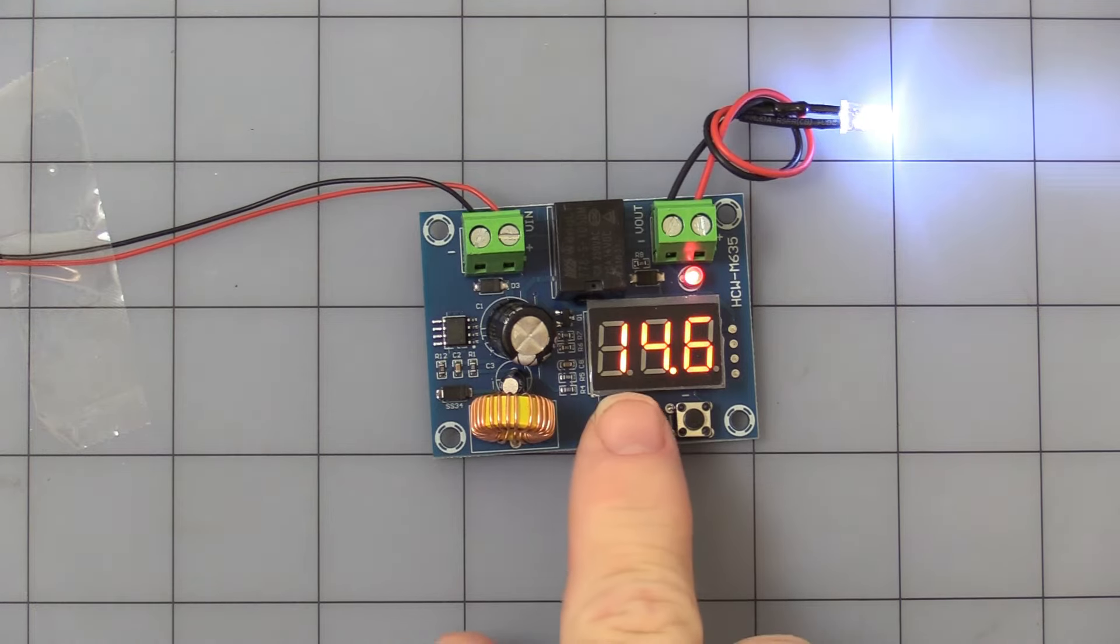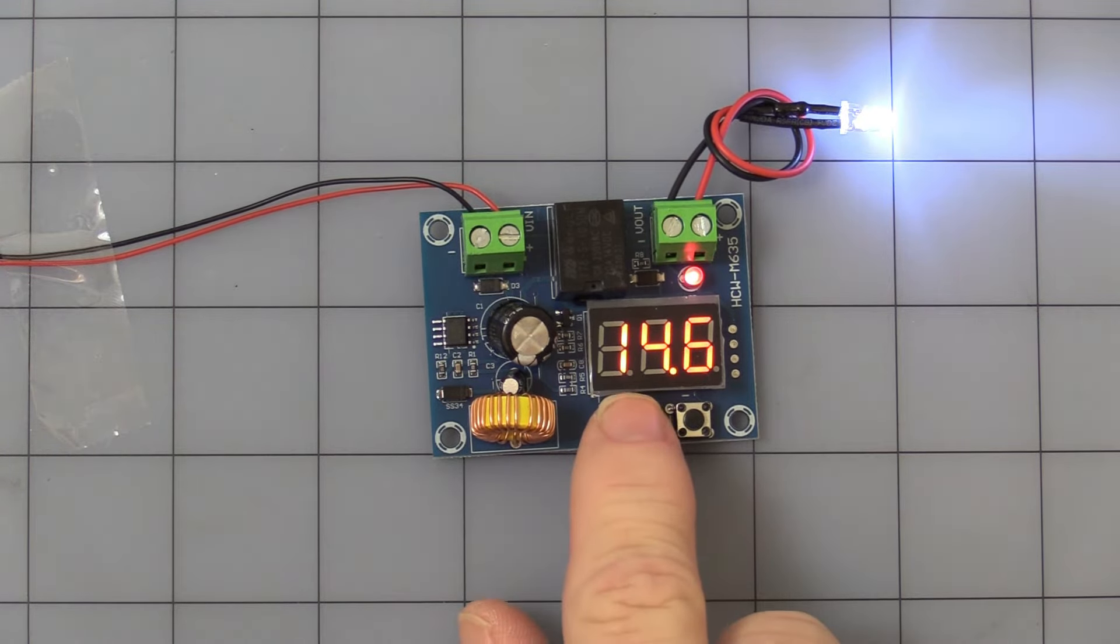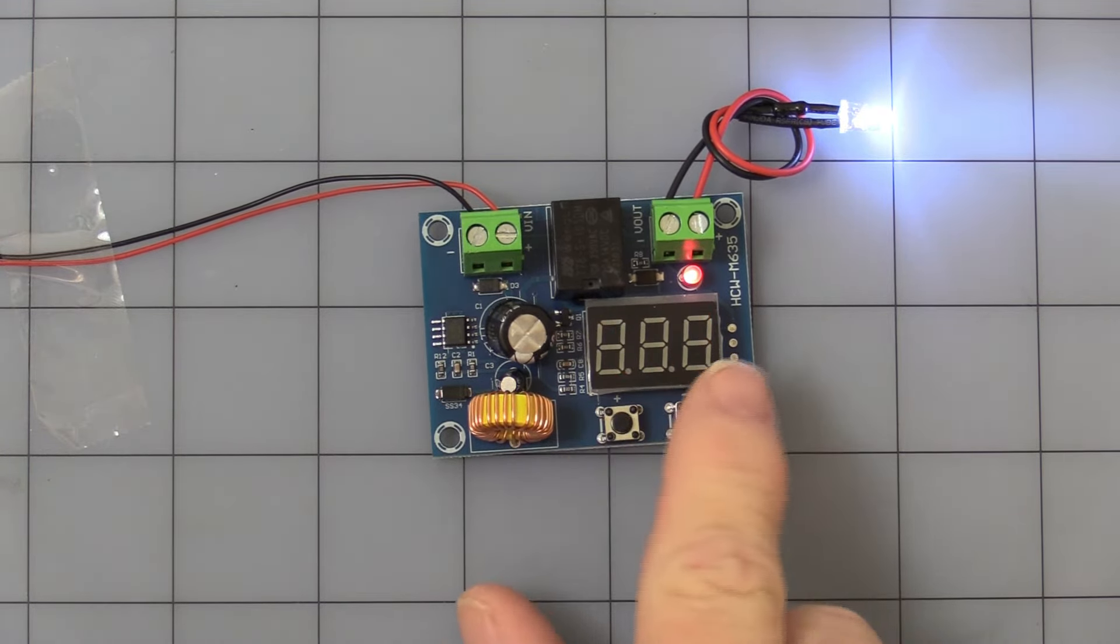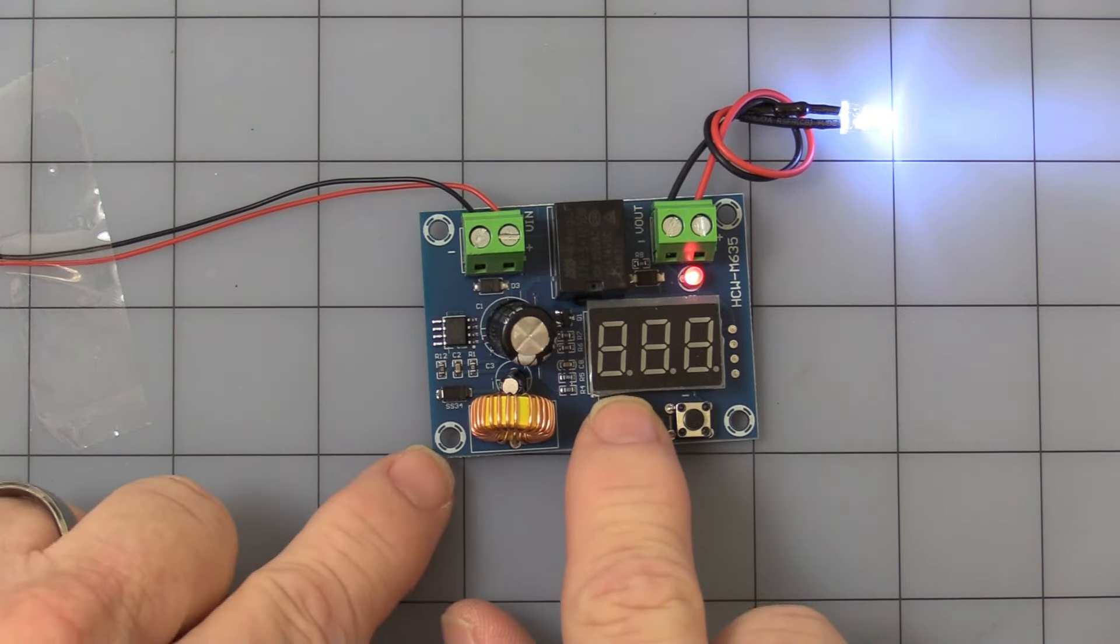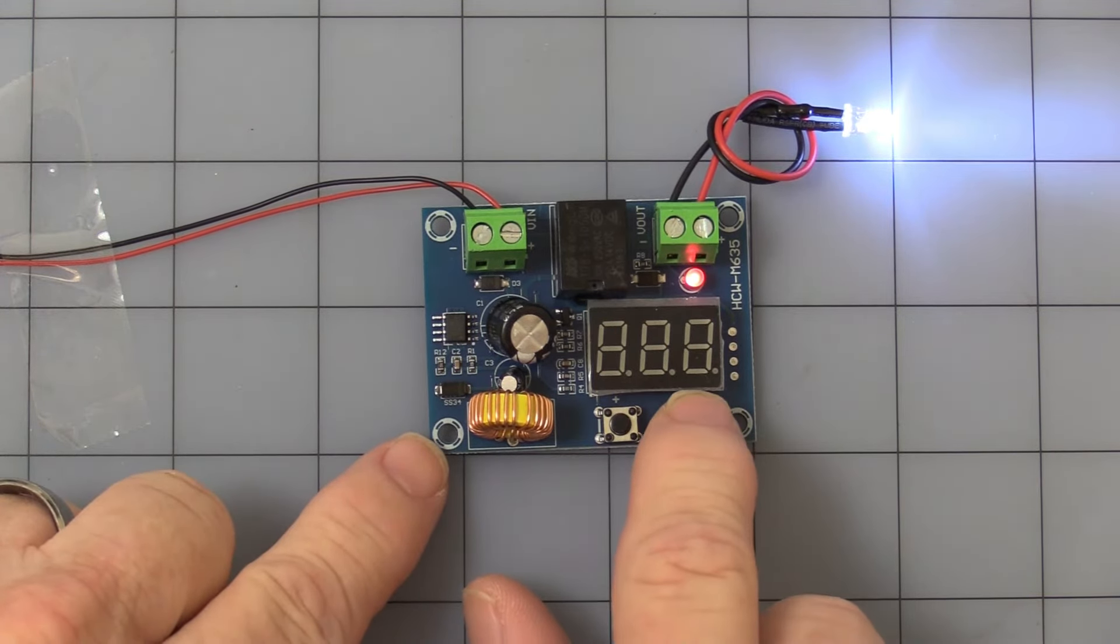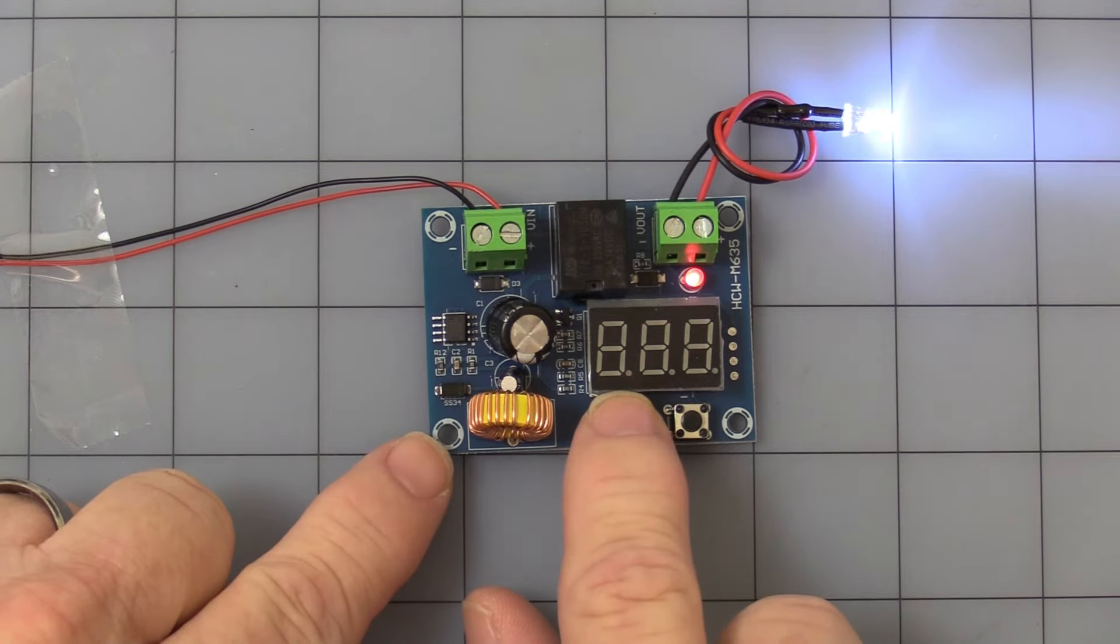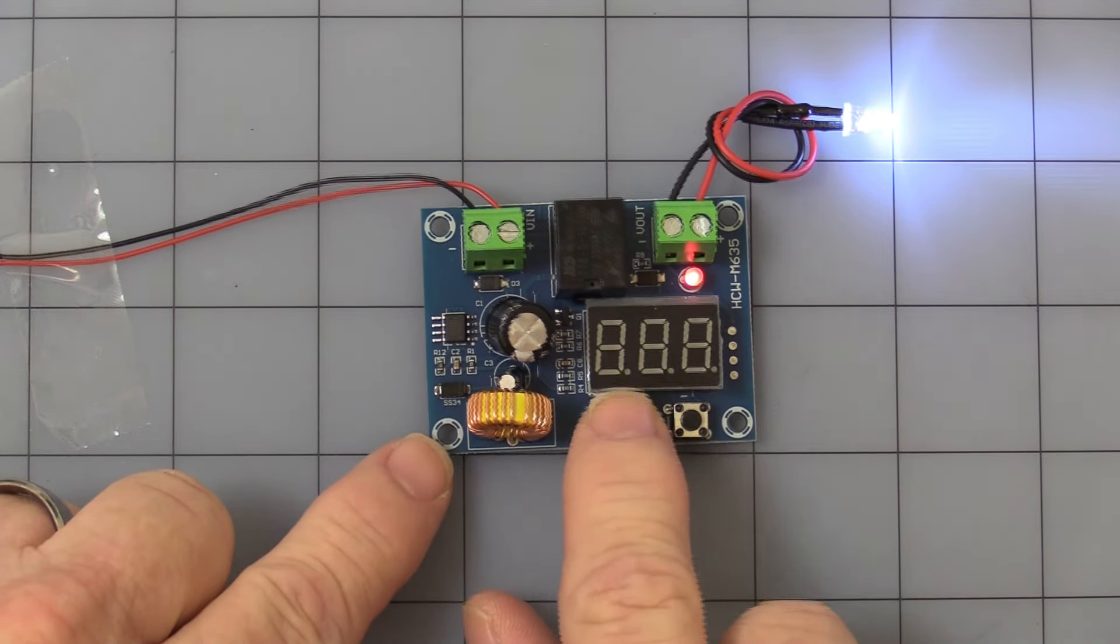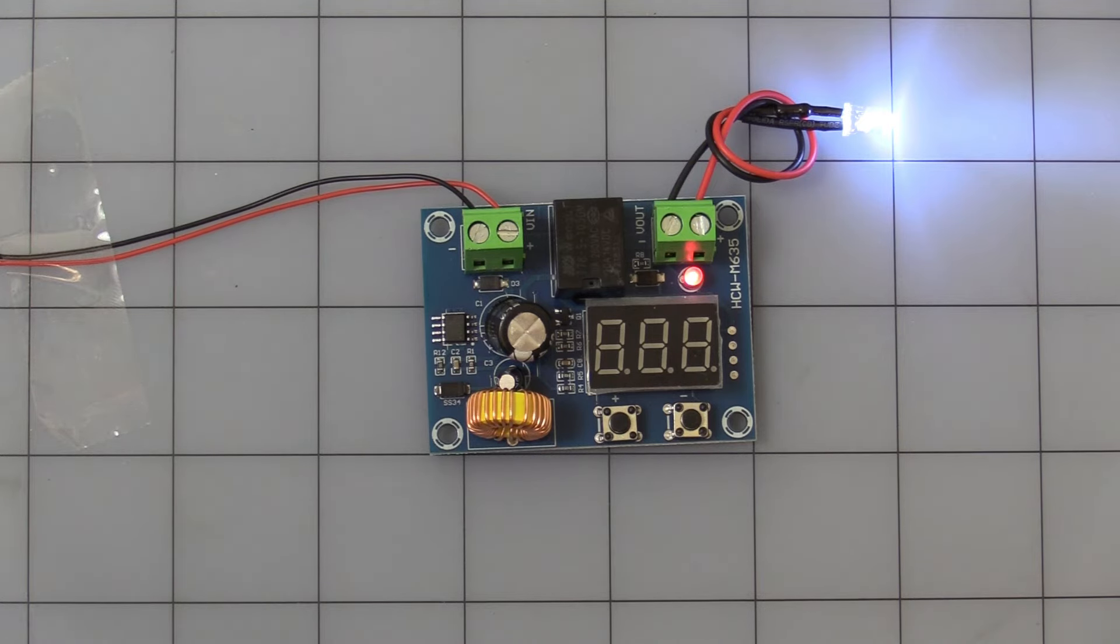Now next, on the same button, if you press and hold, you can actually set a calibration. Now if it's not accurate, if you have voltage drop over a distance, you can change what the actual display voltage is. Leave it alone for a few seconds and it goes back.